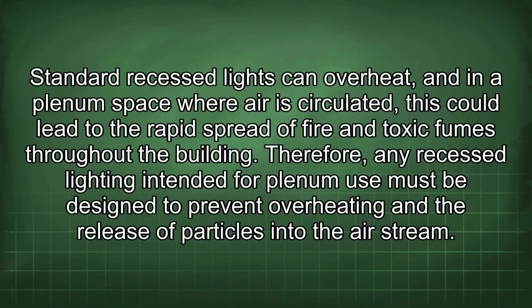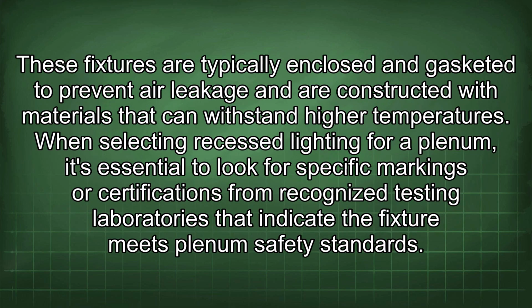Therefore, any recessed lighting intended for plenum use must be designed to prevent overheating and the release of particles into the airstream. These fixtures are typically enclosed and gasketed to prevent air leakage and are constructed with materials that can withstand high temperatures. When selecting recessed lighting for a plenum, it's essential to look for specific markings or certifications from recognized testing laboratories that indicate the fixture meets plenum safety standards.